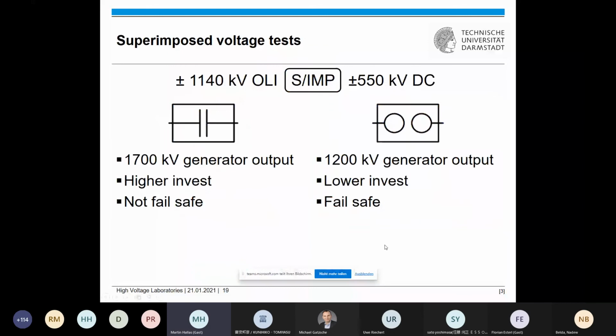Now, the last question is superimposed voltage tests. There are also generally two possible technical solutions to make such tests. So we want to perform 1140 kV OLI tests with 550 kV DC. There are two solutions. They were not presented yet, but perhaps you already know this. You can use a coupling capacitor or you can use a spark gap. A coupling capacitor adds the impulse voltage to the DC voltage. The spark gap directly connects the impulse voltage to the device under test. And there you also see the two differences.